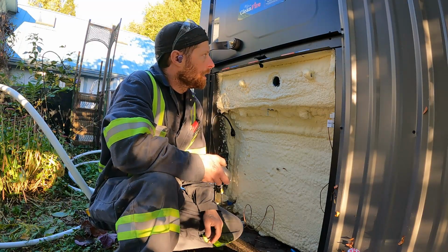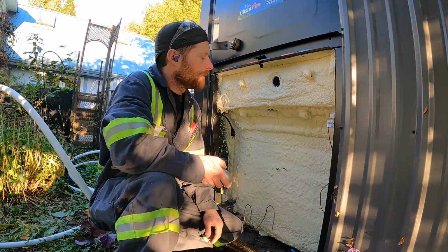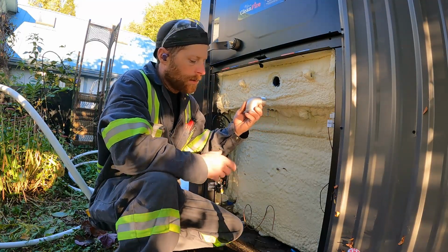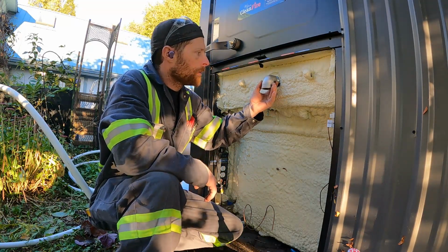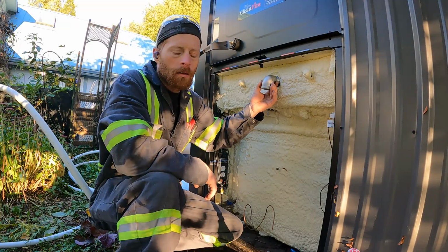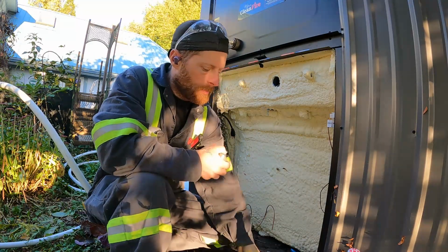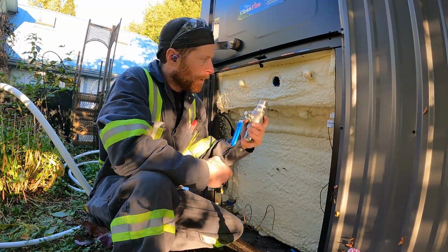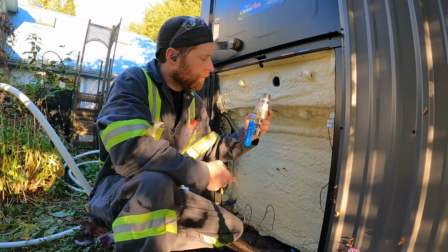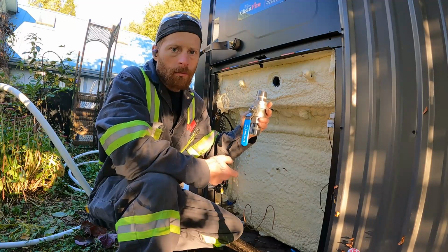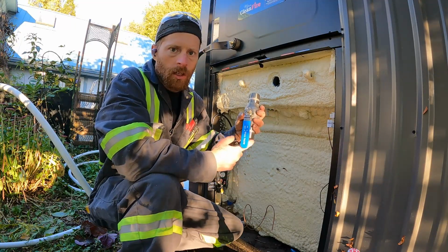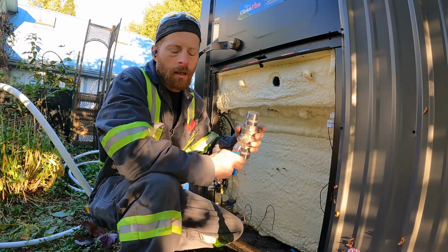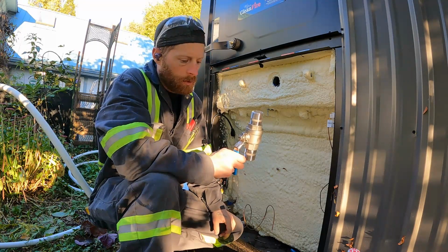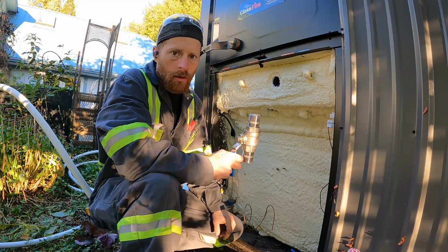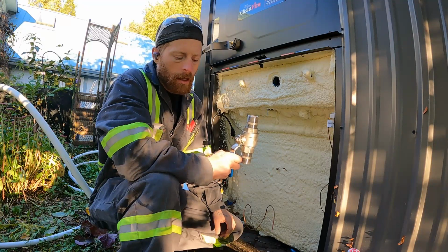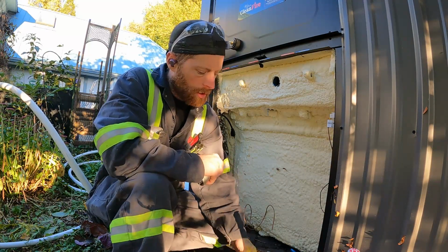So we'll do the inlet first. It's fairly basic, other than the check valve I don't have. We're going to do a 90-degree 1.25 inch street elbow, followed by a 2 inch nipple. Then we're going to go to a 1.25 inch ball valve, then another 2 inch nipple. Then we'll run our check valve, then a 1.25 to 3/4 bushing, and then right to our 1 inch PEX.